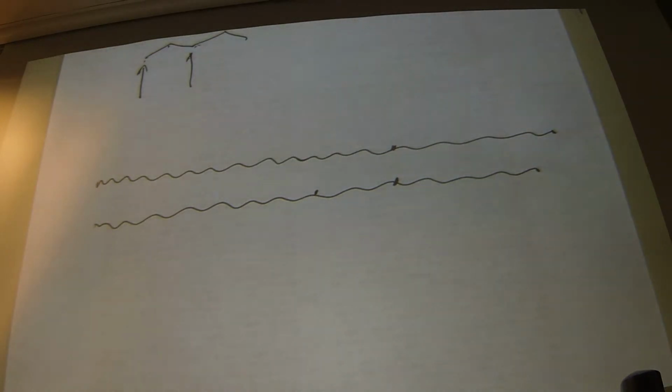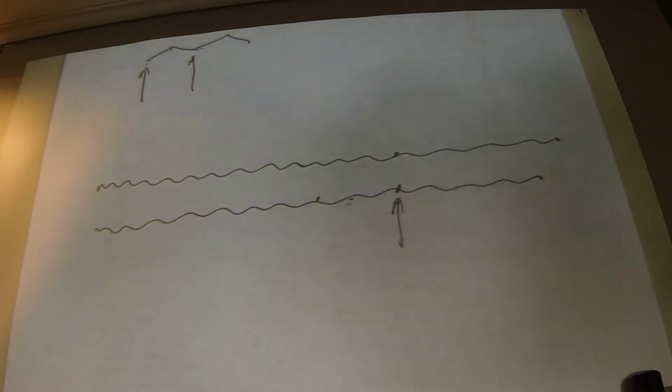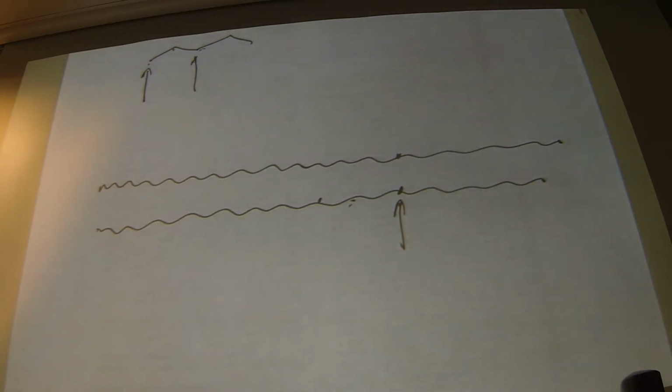Now what you do is after you've done this literally about 10,000 times, you take all these spectra and then you add them up. Now you say, why is that going to work? Here's why it works. Because if I have a peak here, then in every spectrum, I'm going to see that peak. If it's noise, then in some spectra, the noise will be going above the baseline, and in some spectra it will be going below.